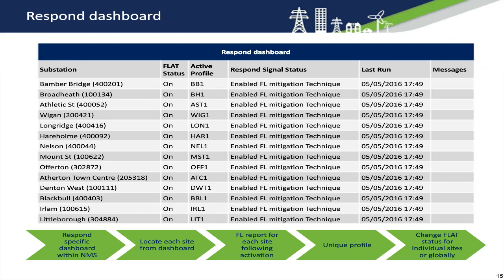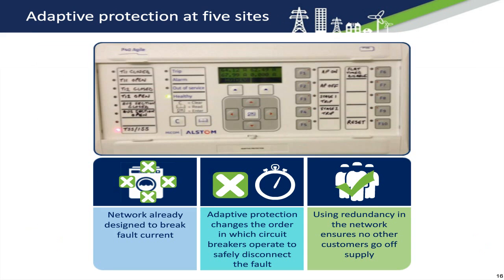The first technique I would like to talk about today is adaptive protection. This is also known as sequential tripping. As I mentioned before, our network is already designed to break fault current and isolate the faulted section of the network using circuit breakers and other protective devices. Adaptive protection changes the order in which the circuit breakers operate to safely disconnect the fault from the rest of the network. Using the redundancy built into the network, we can ensure that no other customers will go off supply as part of this change.